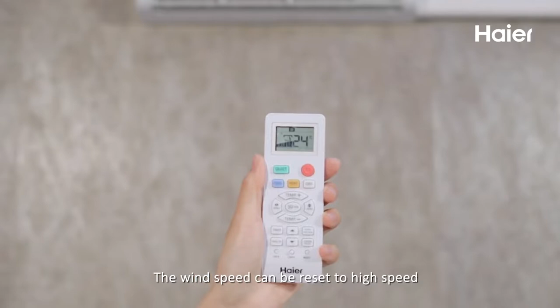Air conditioner runs in cooling mode for a long time in humid environment. The wind speed is set as low wind speed, and the air guide plate is downward position for a long time, which will cause condensation water to be generated on the outside of the air guide plate. The wind speed can be reset to high speed, and the direction of the guide plate can be adjusted to the horizontal direction.